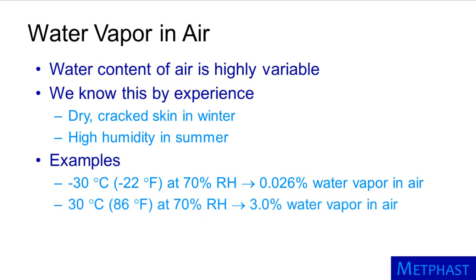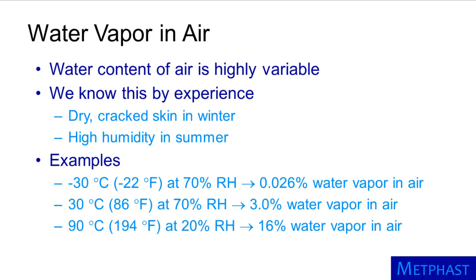At a temperature of 30 degrees Celsius (86 degrees Fahrenheit) and 70% relative humidity, water vapor would be about 3% of the atmosphere, higher than argon. This condition is common in Minnesota and many other places during the summer. In an industrial drying process, you may have very high temperatures with significant amounts of water vapor present. For example, at 90 degrees Celsius (194 degrees Fahrenheit) and 20% relative humidity, water vapor would comprise 16% of the air, nearly as much as oxygen.